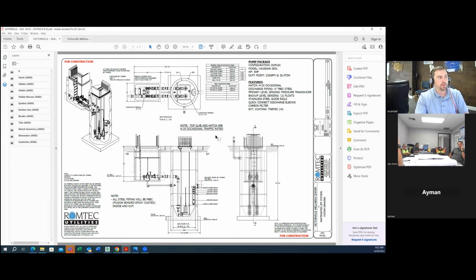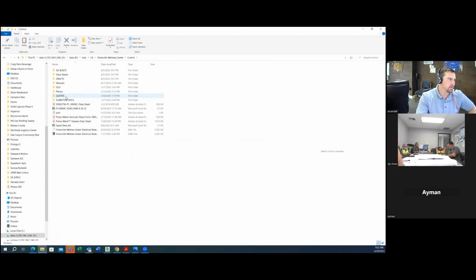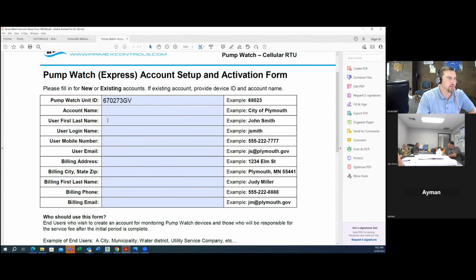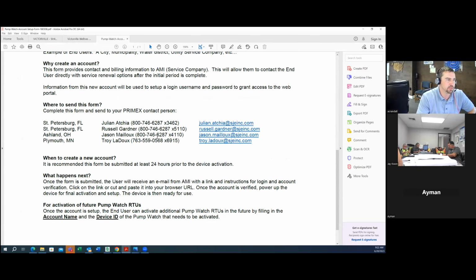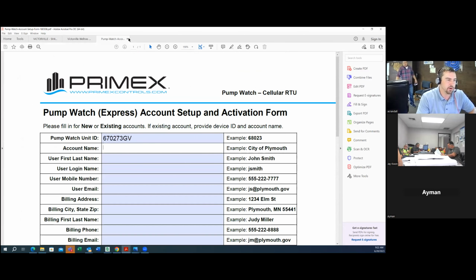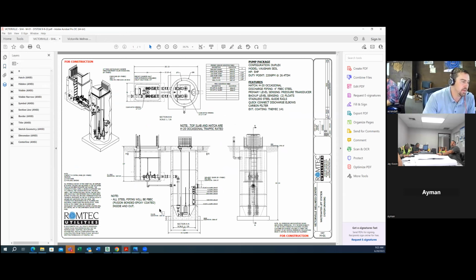All right, what's the cell phone data transmission communications for? Alarming? Yeah, the SCADA alarms. It looks like we have a pump watch system built by Primex. If the city is going to be the owner of this station, they'll have to set up and activate an account for this pump watch system, which essentially dials a cell phone number and, through text message or a robot voice, alarms the operator as to what's happening with the system. We'll need this account set up ahead of time to verify that it's working when we get to startup.